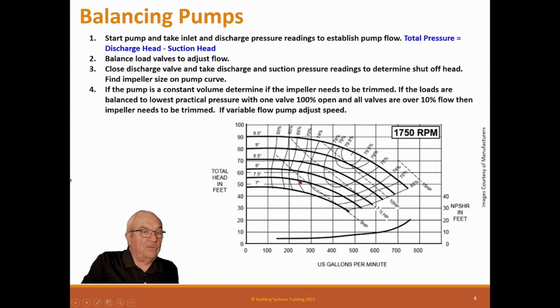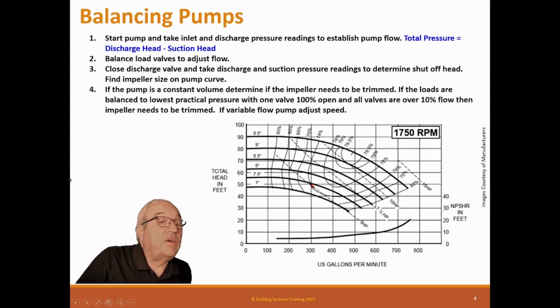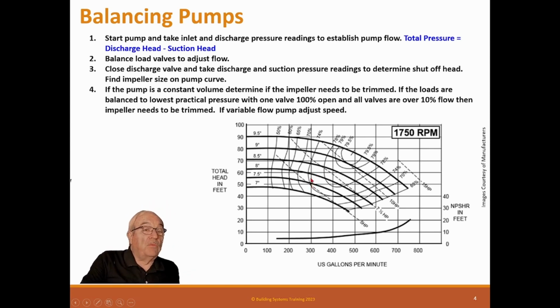Now, if you need to do different, then what you do is, if right now your pump system is pulling 400 at the pressure you need, and you only need 300, then you just go over here and you notice that, okay, it was here at this 8-inch impeller. Now I need a 7.5-inch impeller, or it might work out to 7.6. Now, you say, well, I can't actually see that on this curve. So, how do I tell it to get it to a tenth of an inch?